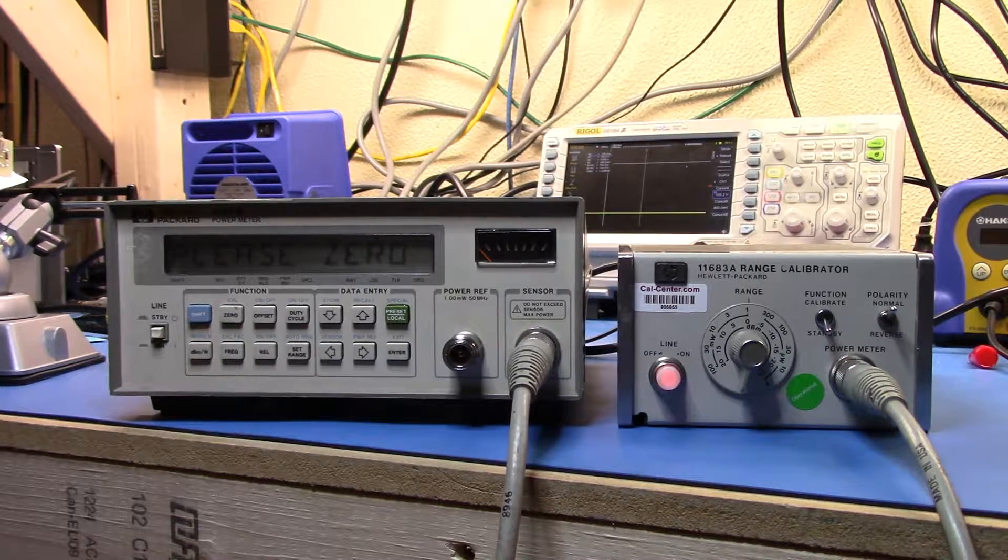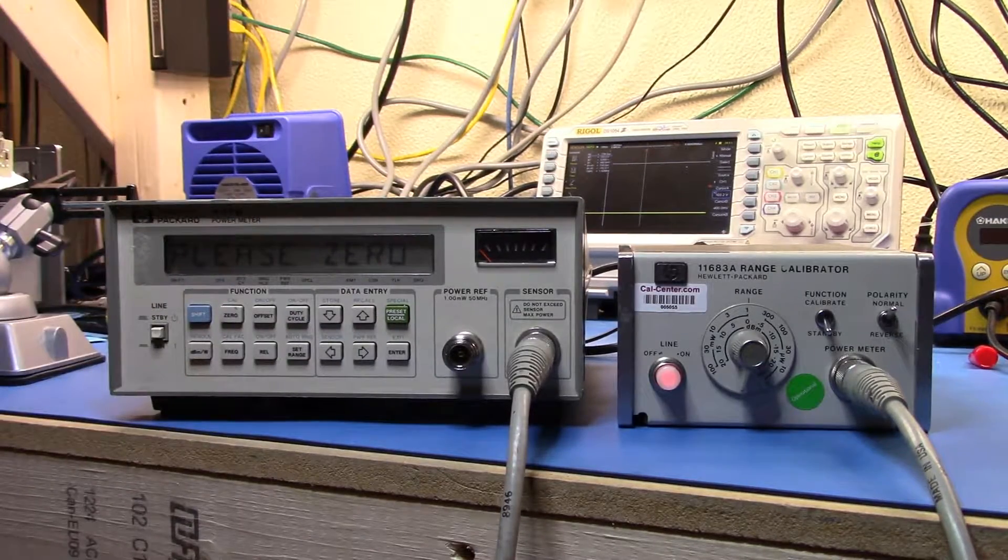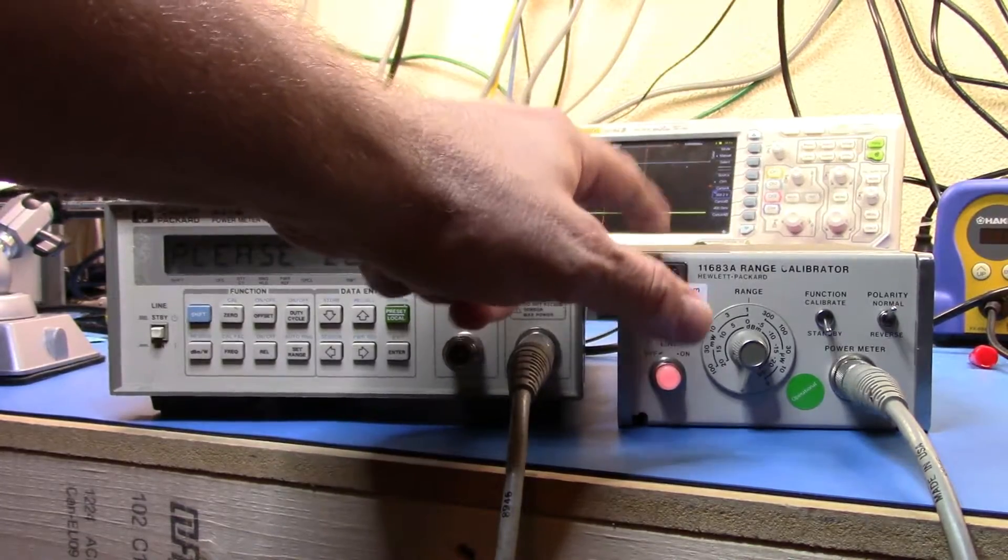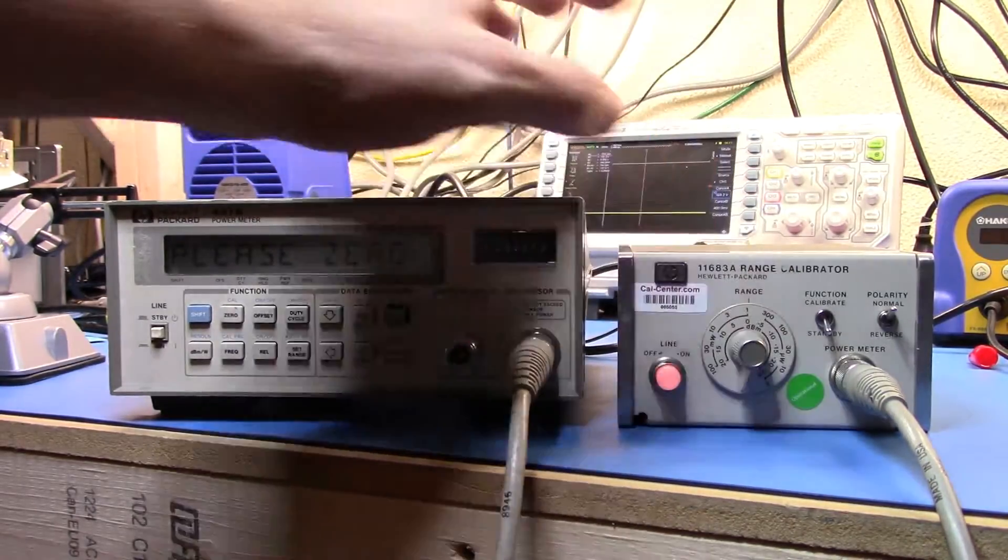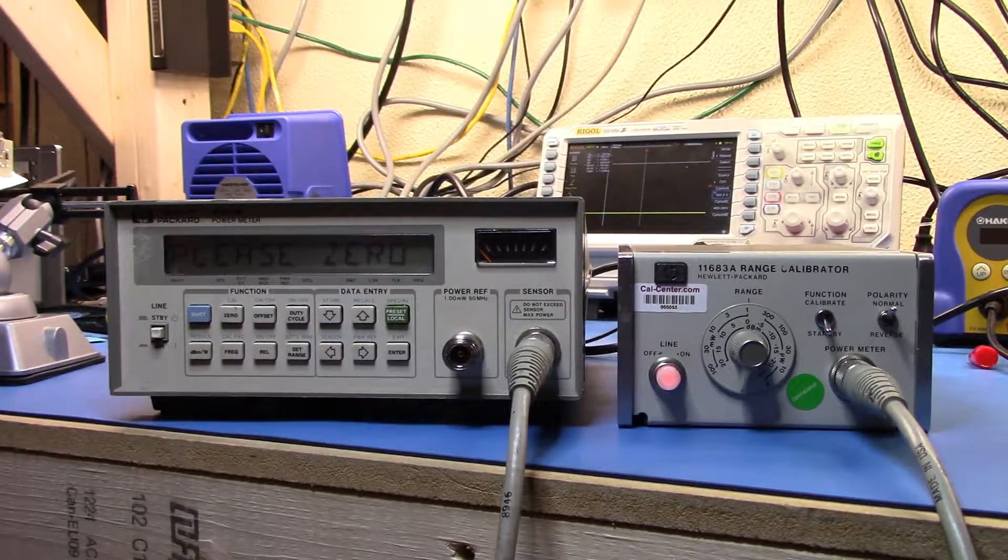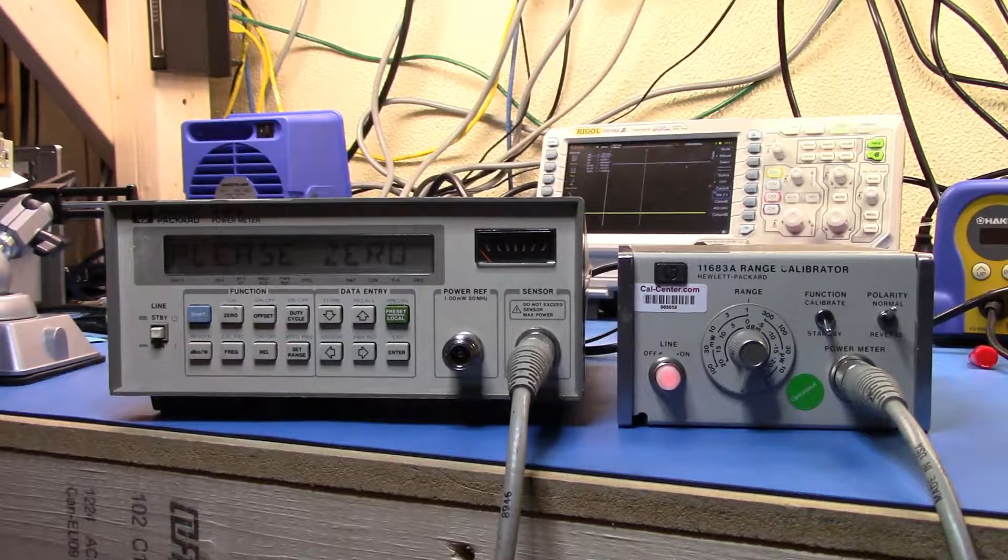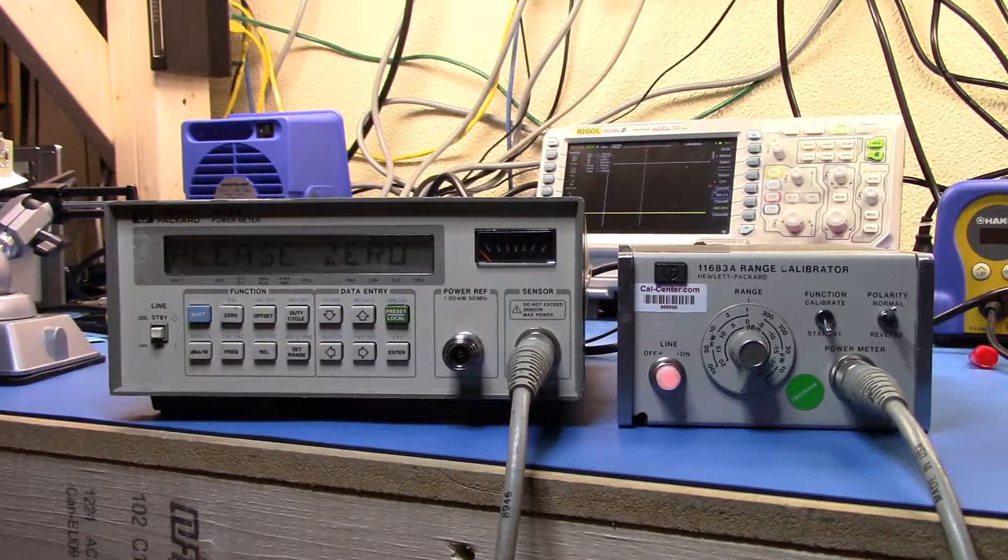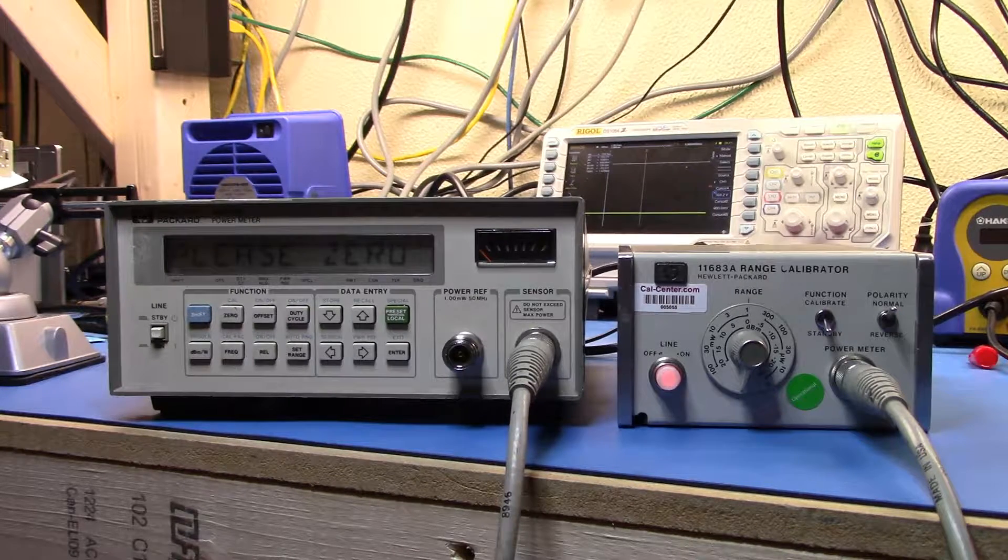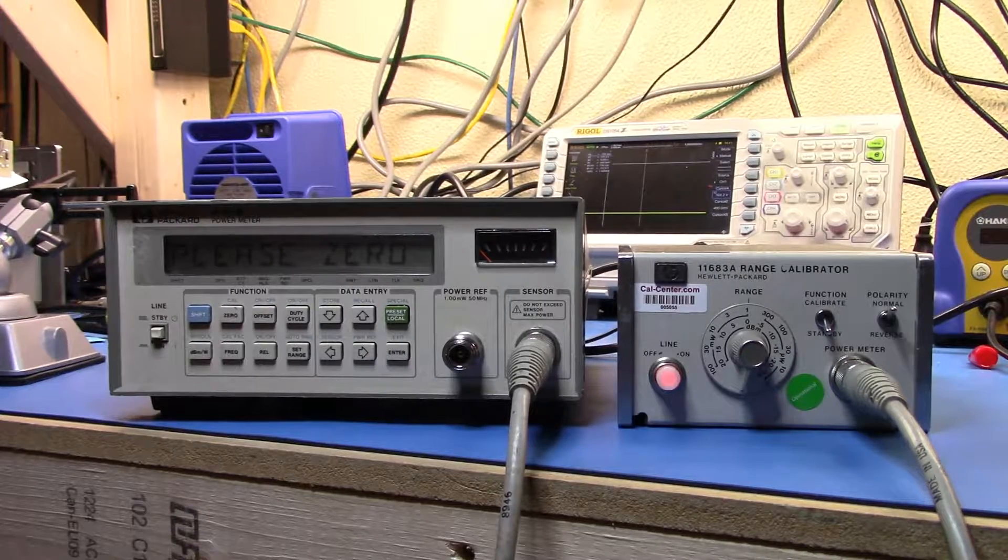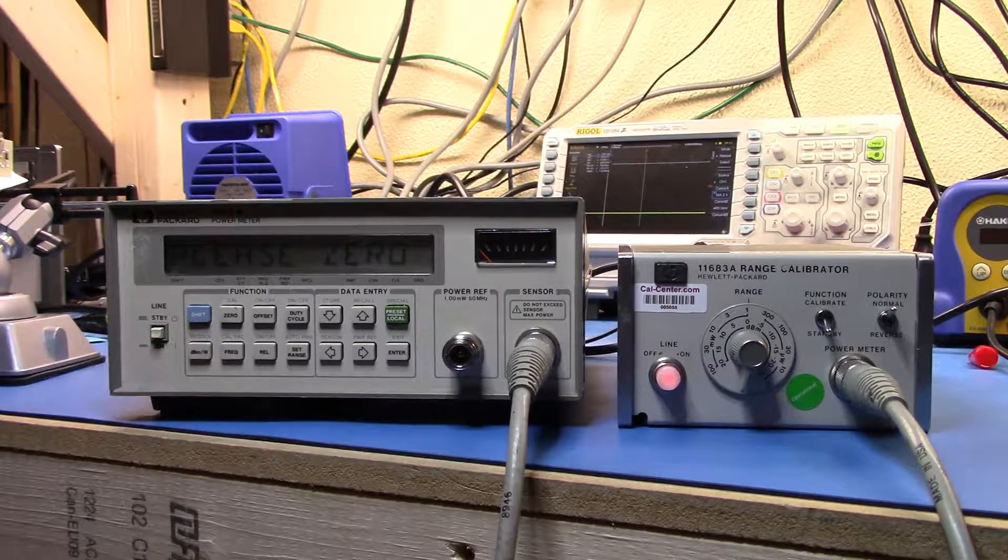Okay, here we are with my dad's 437B and what I've got it hooked up to here is an 11683A range calibrator. This is a piece of kit that's specifically designed to calibrate these series of power meters and this particular one I purchased from CalCenter Calibration Lab down in Texas that was able to get it to me and have it calibrated so I'm fairly happy with where that stands. So what I wanted to do now was just run through the performance tests for the 437B and see how they go.